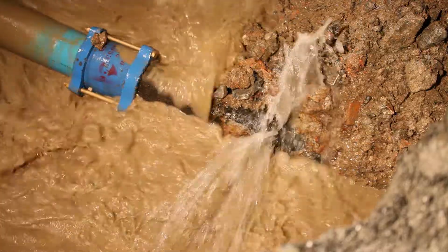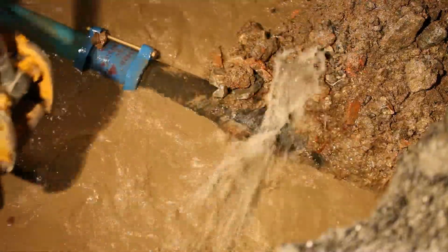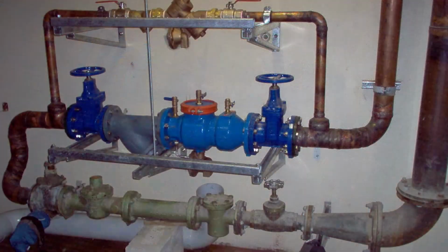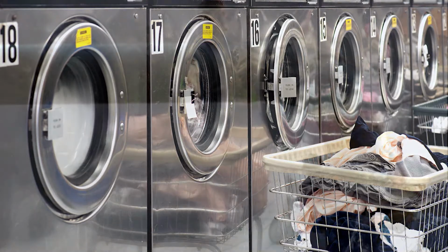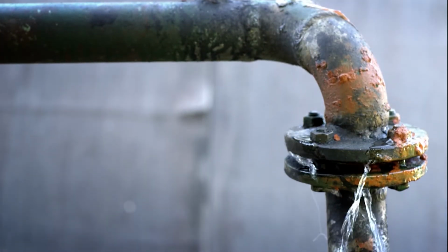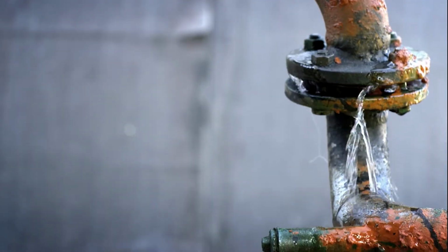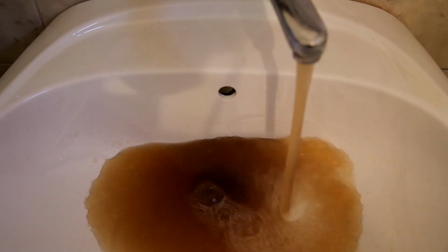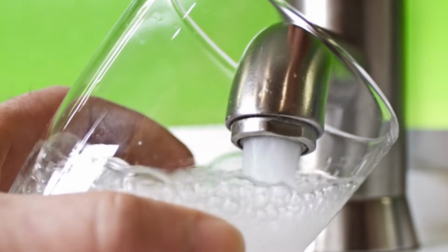Commercial and industrial facilities whose operations present a risk of endangering the public health due to backflow are typically required to have a testable backflow valve installed on their water service line after the water meter and before any branches in the line. Businesses such as restaurants, car washes, beauty salons, and laundry facilities are all examples of potential backflow threats. There are different types of devices designed for different types of hazards posed to the drinking water supply, and water providers can have differing guidelines.